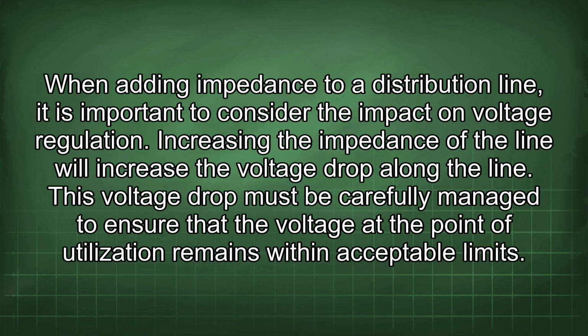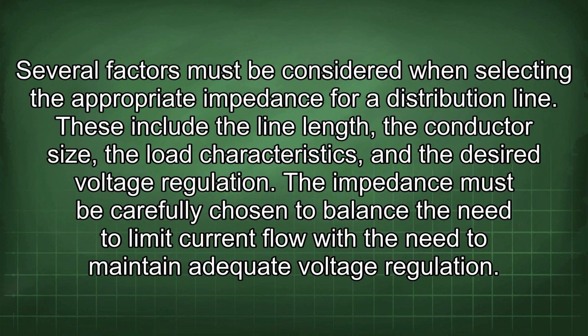When adding impedance to a distribution line, it is important to consider the impact on voltage regulation. Increasing the impedance of the line will increase the voltage drop along the line. This voltage drop must be carefully managed to ensure that the voltage at the point of utilization remains within acceptable limits. Several factors must be considered when selecting the appropriate impedance for a distribution line.